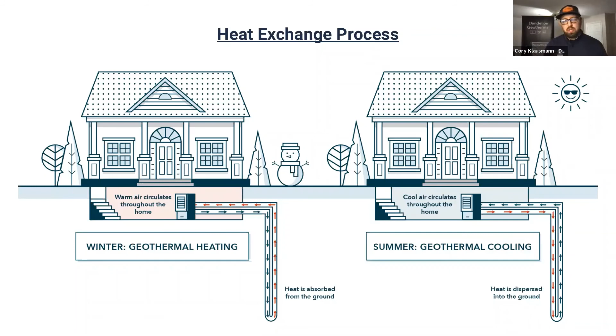We're really drilling down between 1 or 2 holes, depending on the size of the house, for an average home, going down between 350 and 450 feet deep. These pipes are made out of high density polyethylene - they're corrosion resistant and come on a big spool, which is nice, so there aren't a bunch of different connection points to worry about. It's really just one long continuous pipe into the hole, and at the top it's one connection that we bring right into the house.